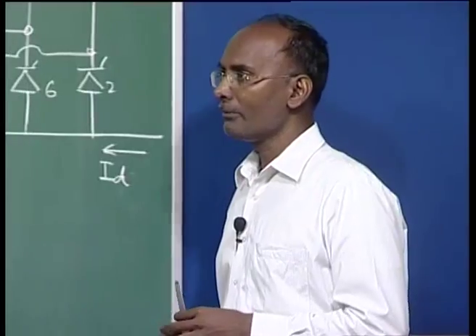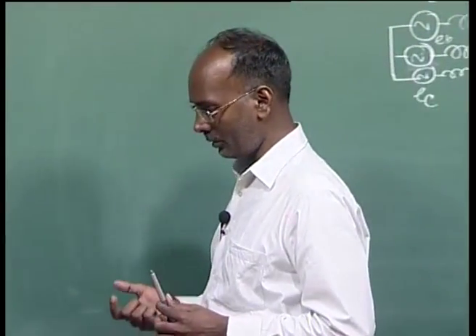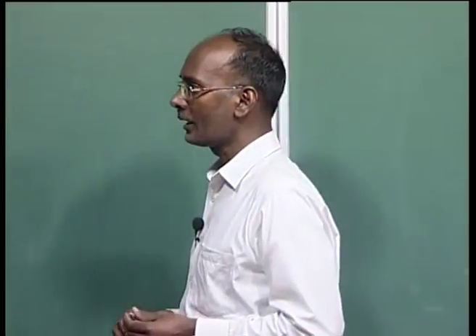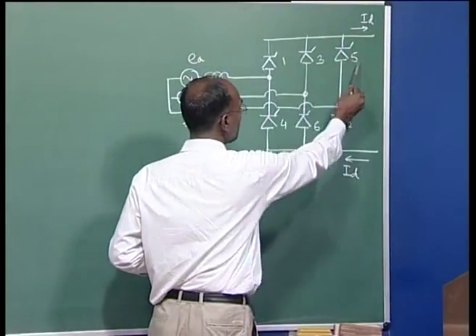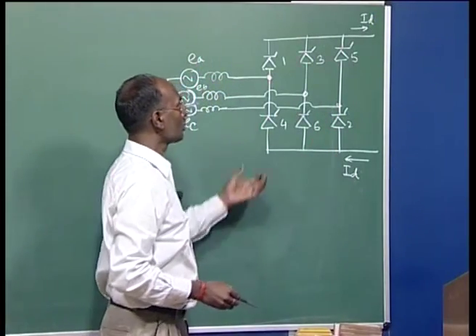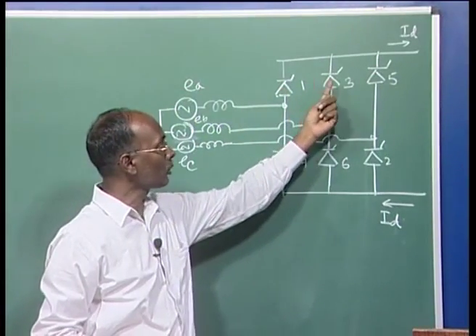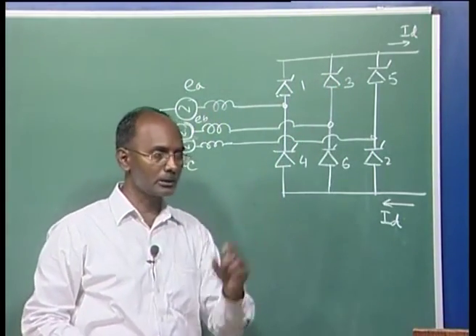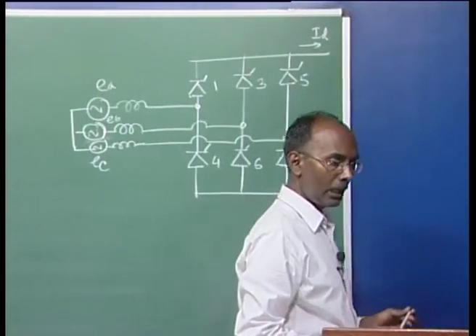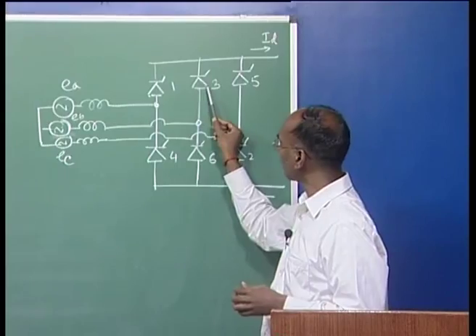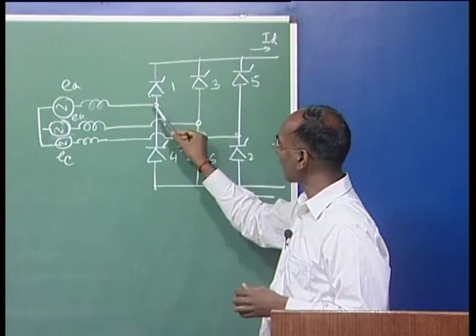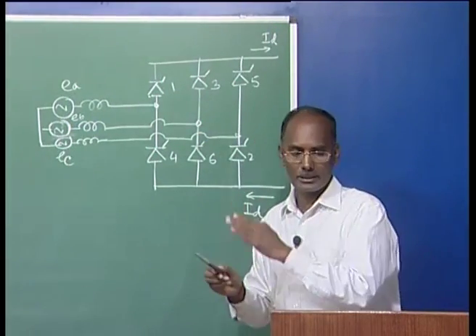Today we discuss when the overlap angle is zero. The overlap angle is defined as the duration when the current is shared by two valves in the same commutation group. There are two commutation groups: upper and lower. When valve current shifts from one to three, that duration is the overlap angle. Here we assume overlap angle is zero, meaning the current shifts instantaneously when the firing pulse is received.